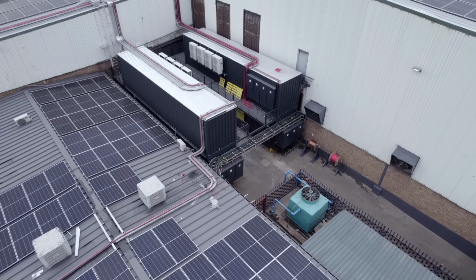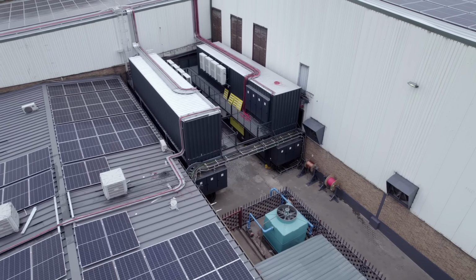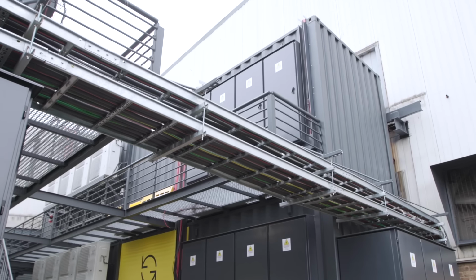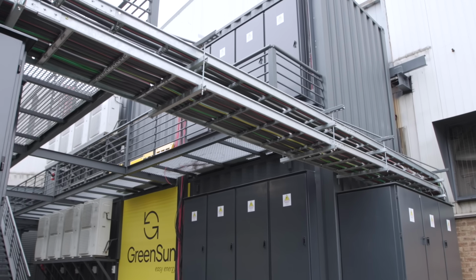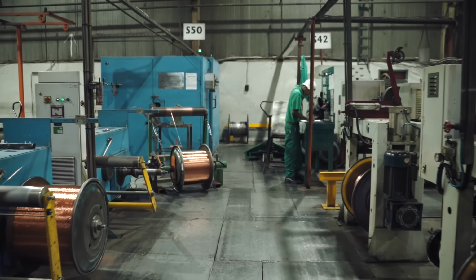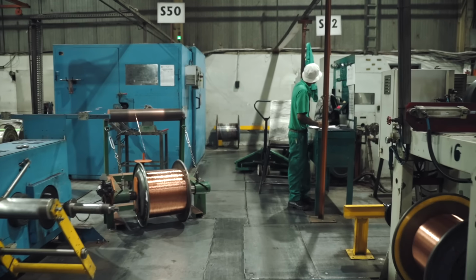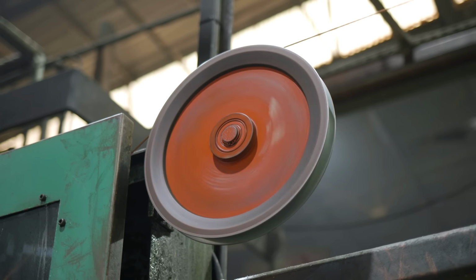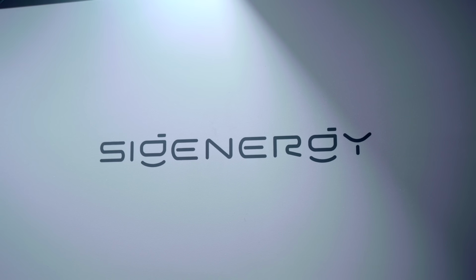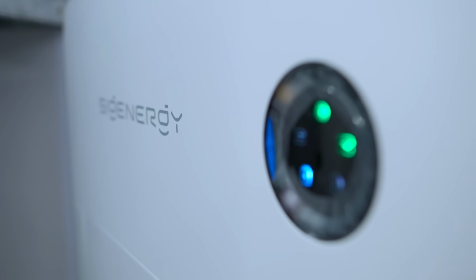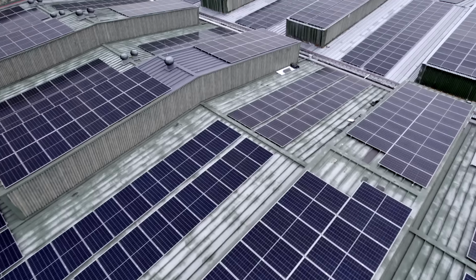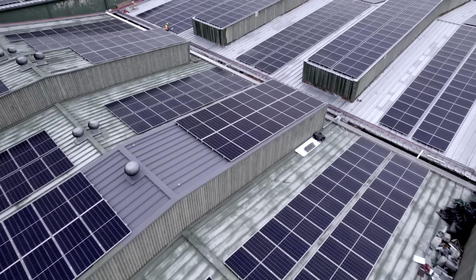What sets this container apart from anything else in the market, I believe, is the changeover time, specifically for this site where they've got very sensitive equipment that can't switch off during any load shedding scenarios. So with the Sigenergy solution, we have a 0 millisecond changeover from grid to off grid. They will have absolutely no downtime during that changeover.